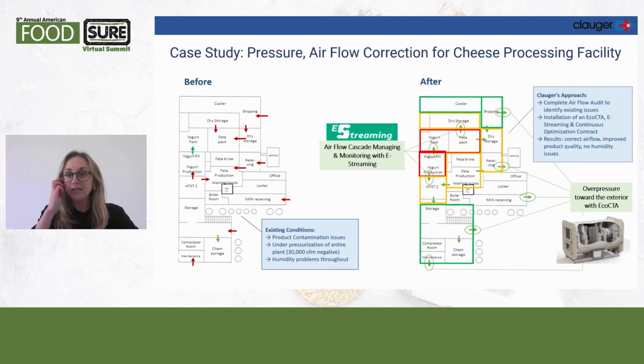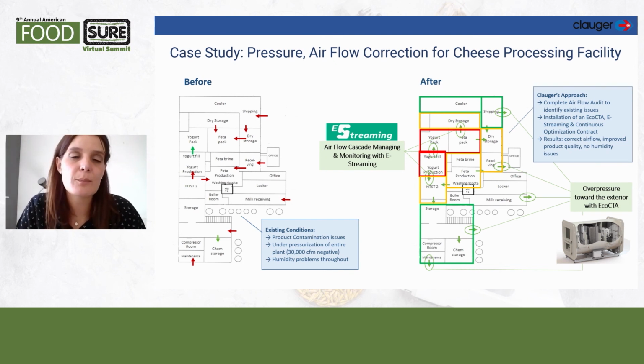Here's a case study showing how to correct the airflow. We performed an audit in a cheese processing facility, and as you can see on the left, the airflow was wrong. You can see the red arrow from the exterior to the plant through the shipping, receiving, milk receiving, and maintenance areas, so there is potential for contaminants from the exterior to come into the plant.